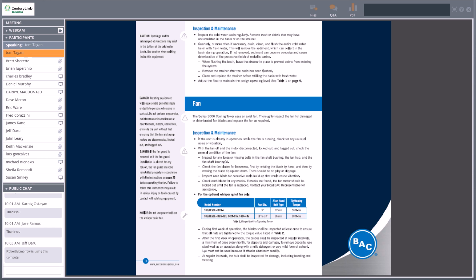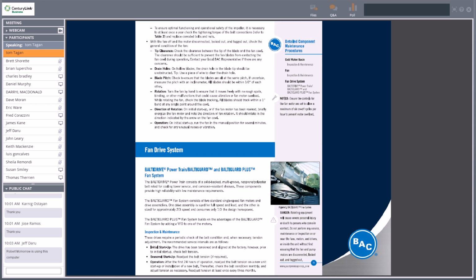Again, more detailed instructions on inspecting the fan. Make sure that the fan blades are not loose. Make sure that they're not cracked. With sound-sensitive situations these days, all manufacturers have 3 different types of fans. Some are galvanized steel, some are an aluminum blade, some are a plastic or almost a fiberglass construction. So you want to just make sure that you don't see any cracks. Make sure that the fan cowl is not impinging, that your fans are not hitting the side or rubbing up against your fan cowl. If so, obviously for safety reasons, you want to shut that down and readjust everything. And again, this is a detailed list of how to go about looking at that.